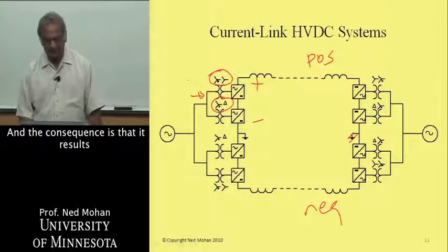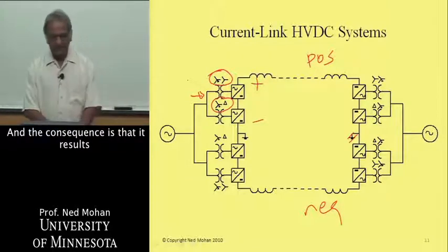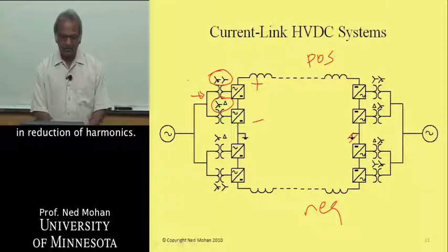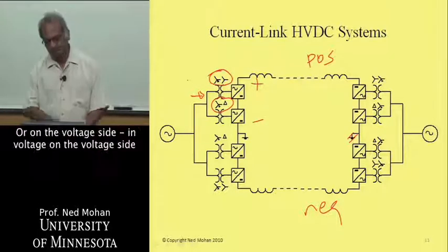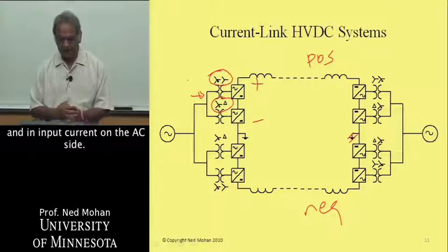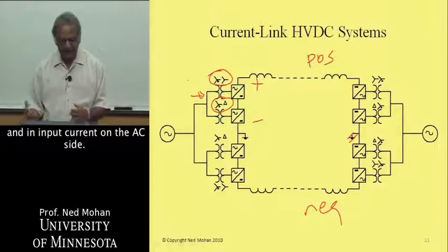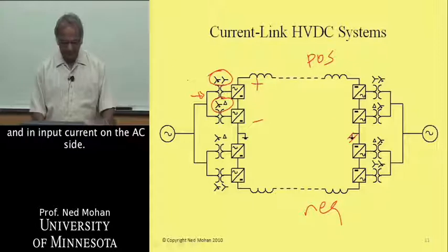The six-pulse operation for the voltage here, and the current here, from six-pulse it becomes 12-pulse. The consequence is that it results in reduction in harmonics, both on the voltage side and in input current on the AC side.